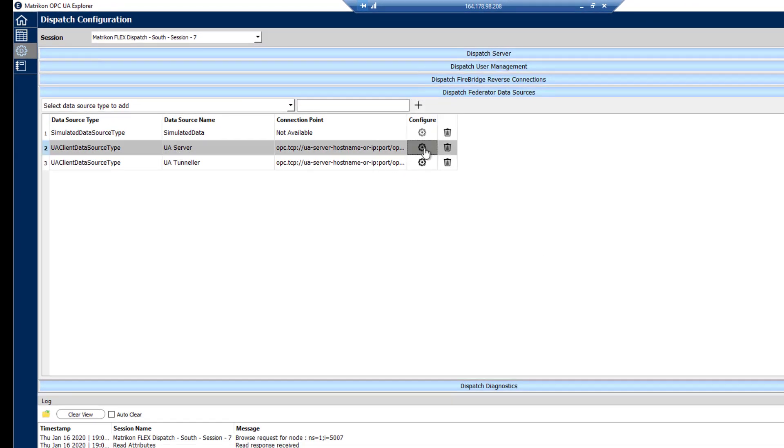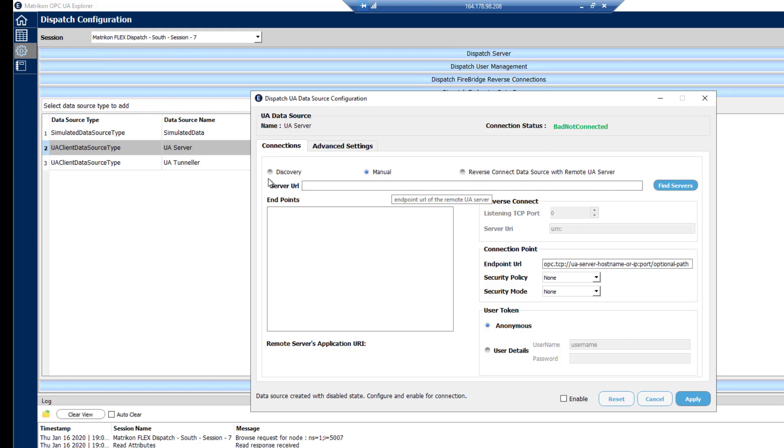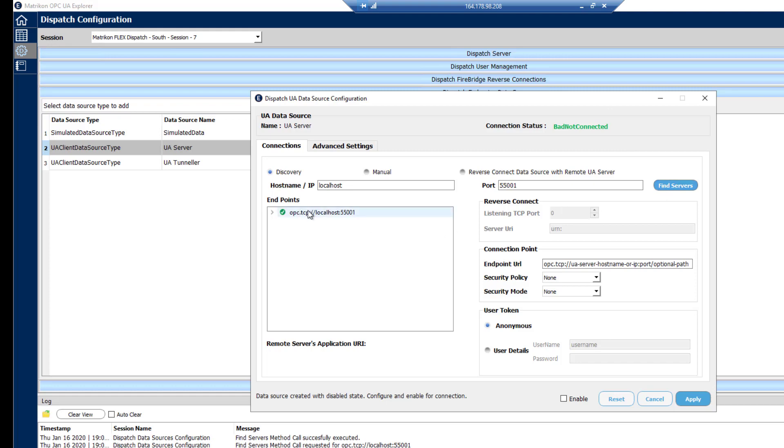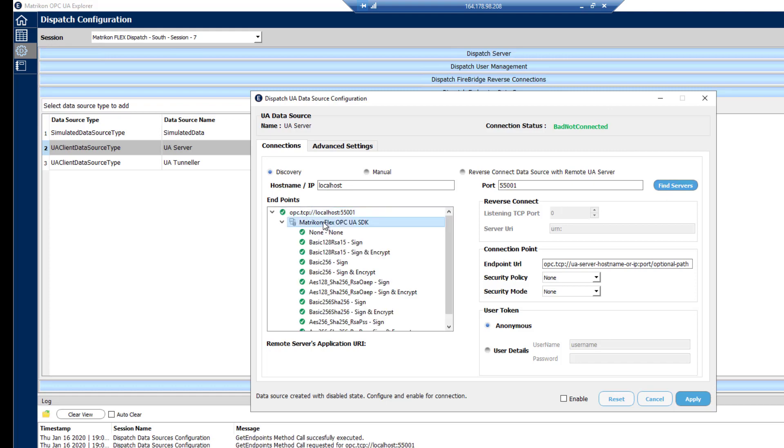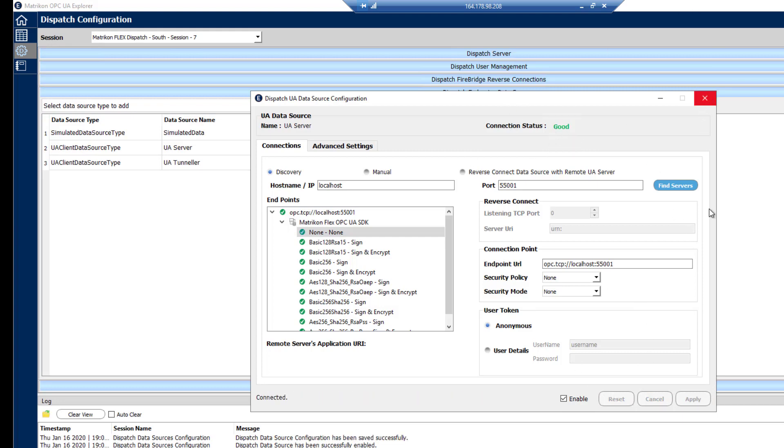These gears here are going to let us do the configurations. So for the UA server, I'm just going to go in here. I'm going to do a manual search for this one. We'll just go localhost. I have it set up on port 55,001. We click on find. We'll find it here. And then we just drill down into it. I'm going to use none encryption and signing on this one. Set it as anonymous. Set it as enabled. And apply that. We should see that go to good. And we're good there.